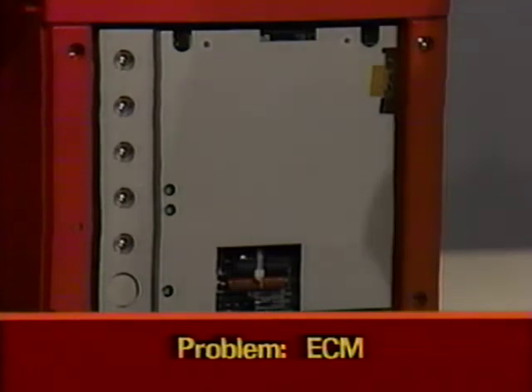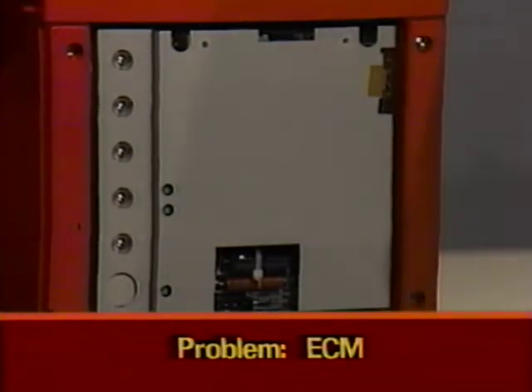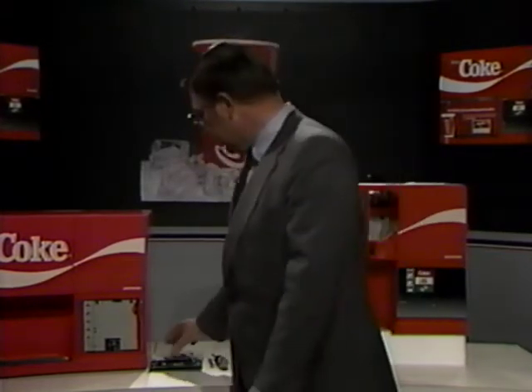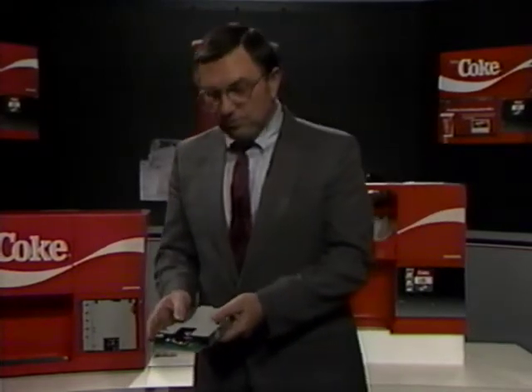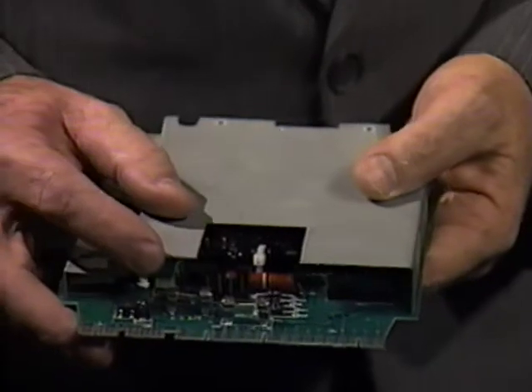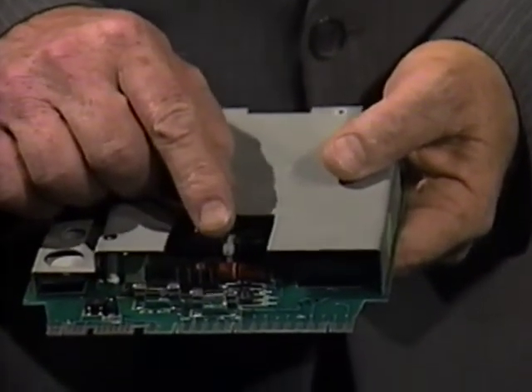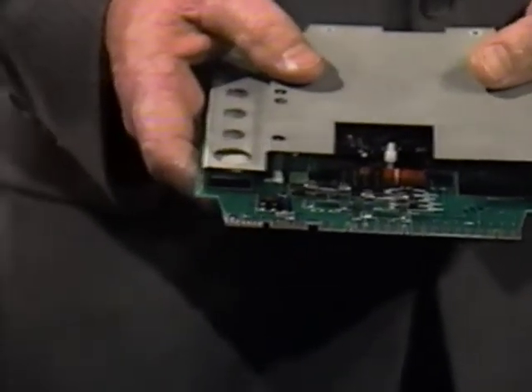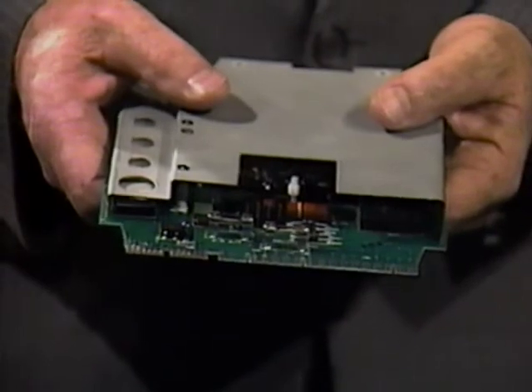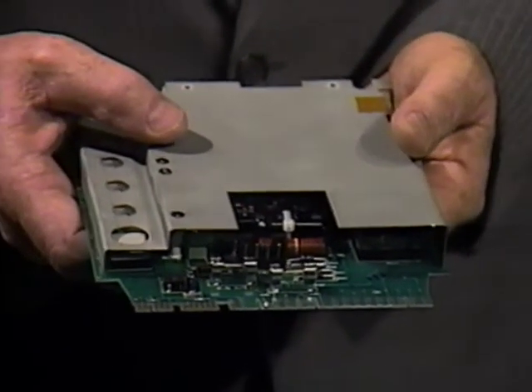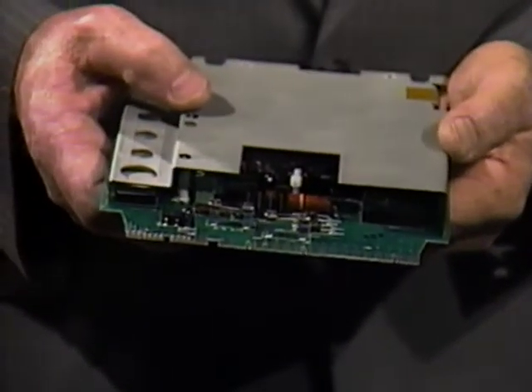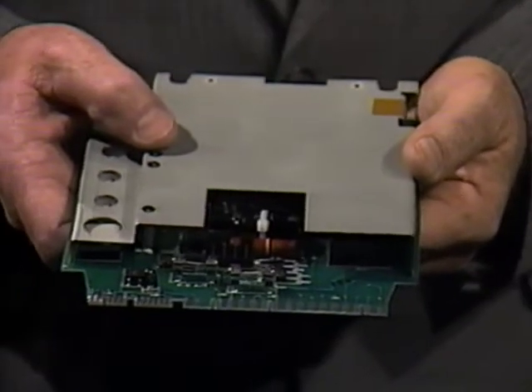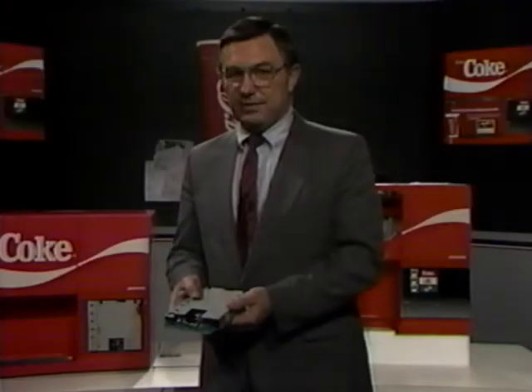The Electronic Control Module, or ECM, is really the mind of the machine. It takes the sensor's input and it takes other commands like buttons being pushed, and it keeps all the systems doing what they're supposed to do. But occasionally something can go wrong with the board itself. For instance, on the board there are two fuses. One is a 2.5 amp fuse. The other is a 100 milliamp fuse, and they will occasionally blow. If you replace them and they continue blowing, then you'll just have to replace the board. Another problem is occasionally internal relays on the board will stick, and again you have to replace the board. It's an easy job to replace the board, and we'll show you how later.